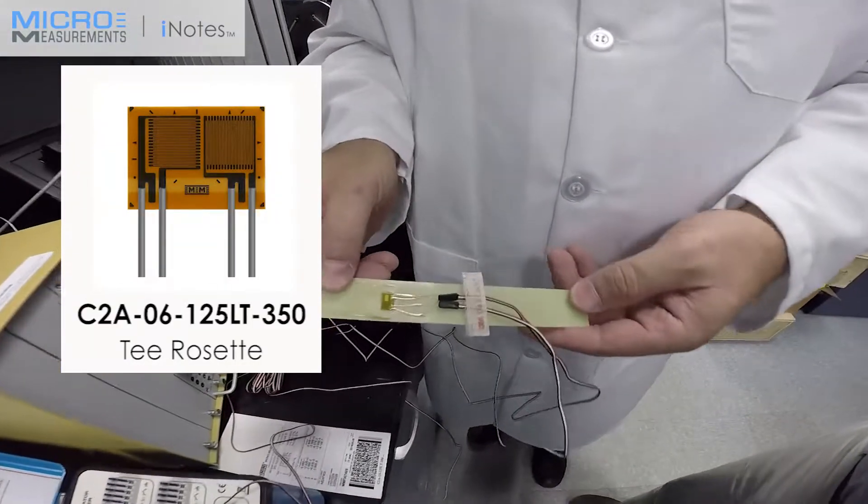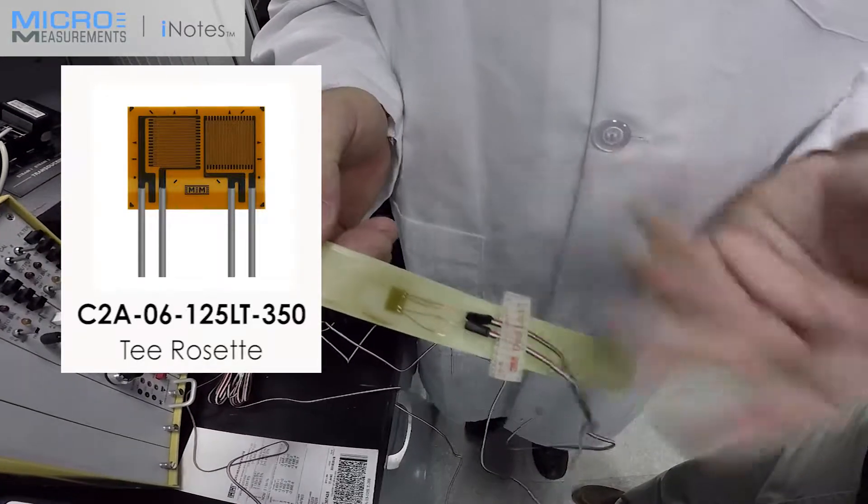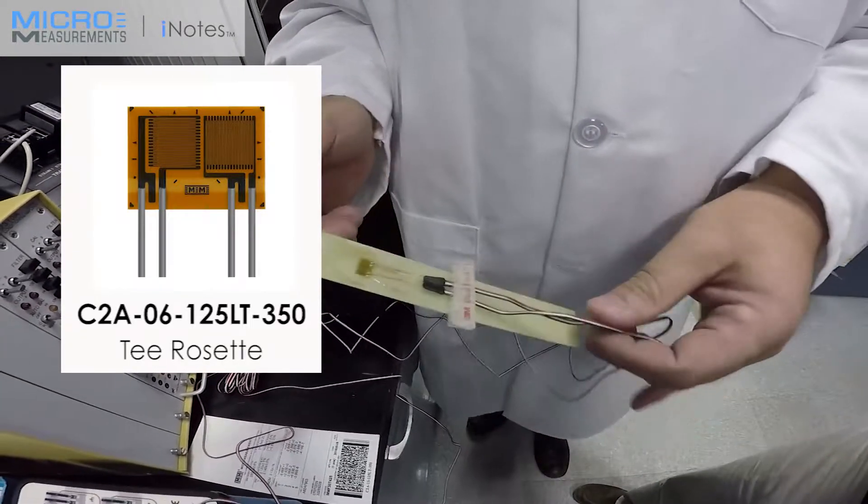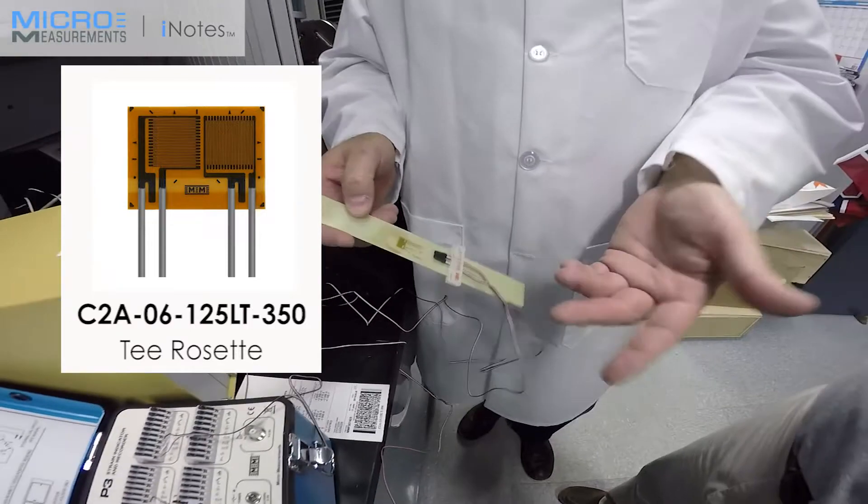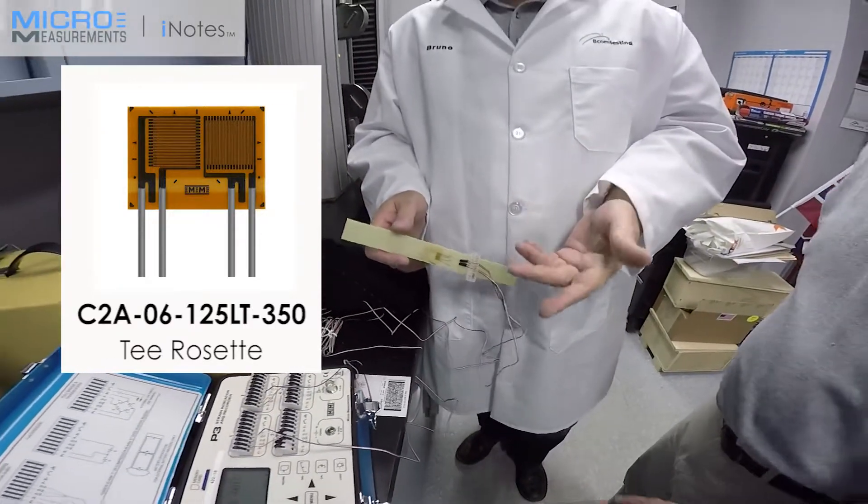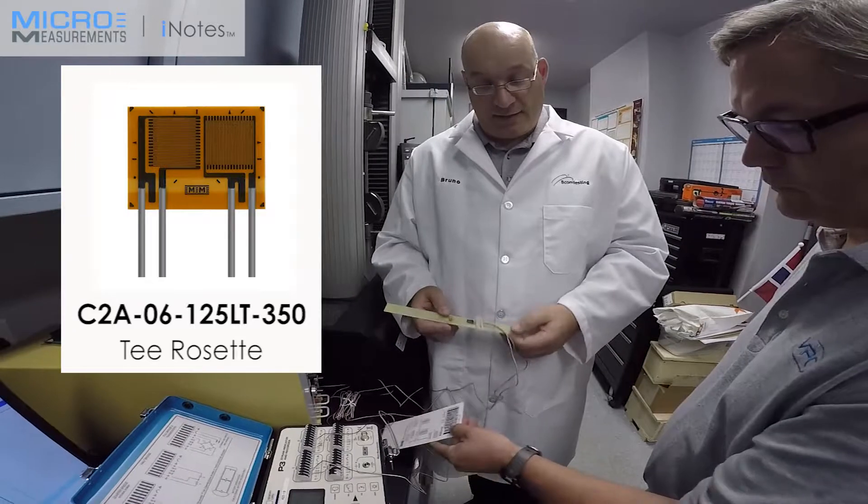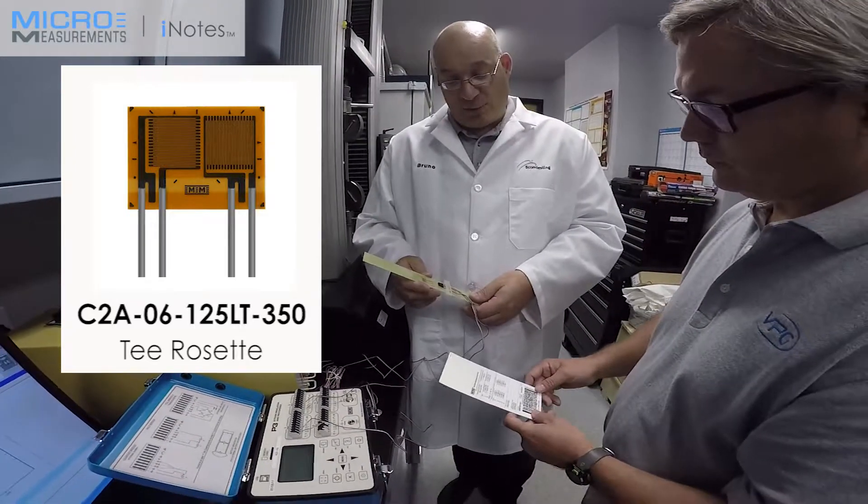Yeah, correct. We use a 125LT in this case, which is already pre-wired as a C2A gauge provided by Micro-Measurements. The pre-wiring helps us to reduce our labor time where we don't have to actually solder connection and cables to the actual gauge.